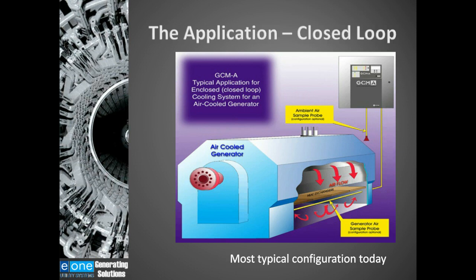Again, it was in the neighborhood of 3 o'clock in the morning. There shouldn't have been any submicron particles in the ambient air. They investigated it and found out that the ambient air had detected overheating in the collector ring of that generator. So there are other benefits to monitoring the ambient air of these generators.